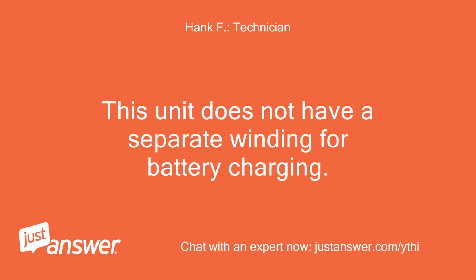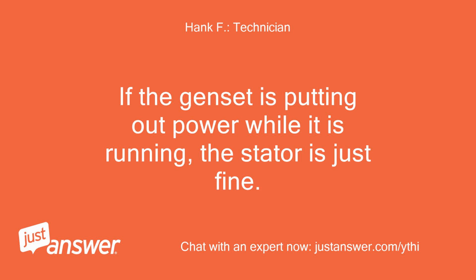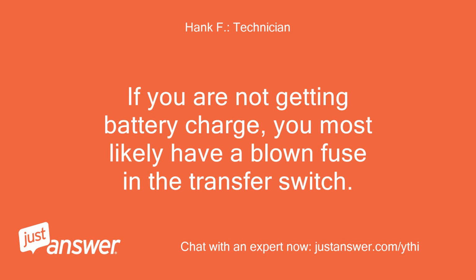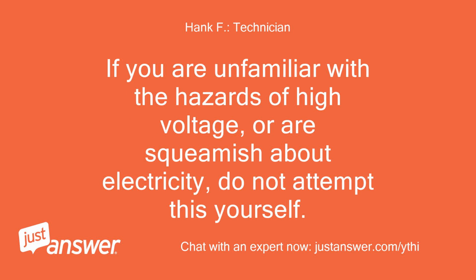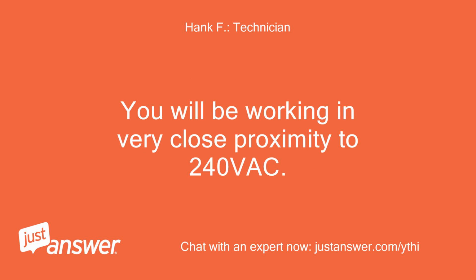This unit does not have a separate winding for battery charging. If the genset is putting out power while it is running, the stator is just fine. If you are not getting battery charge, you most likely have a blown fuse in the transfer switch. If you are unfamiliar with the hazards of high voltage, or are squeamish about electricity, do not attempt this yourself. You will be working in very close proximity to 240 VAC.